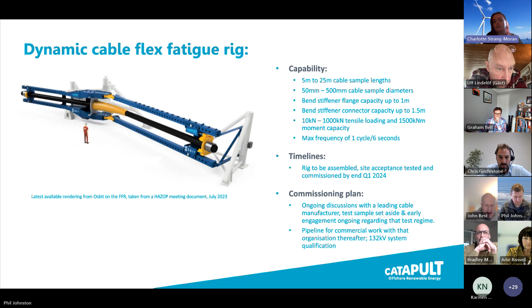So this is one example of some of our rigs. This one is our new dynamic cable flex fatigue rig with capability of samples between 5 meters to 25 meter lengths. We're able to work with samples between 50 to 500 millimeter diameter. It has the ability to test samples with a bend stiffener attached as well, and a maximum frequency during operation of 1 cycle per 6 seconds. This will be commissioned by early 2024 with ongoing discussions with industry to create a pipeline for commercial work towards 132 kV system qualification. Next slide, please, Phil.